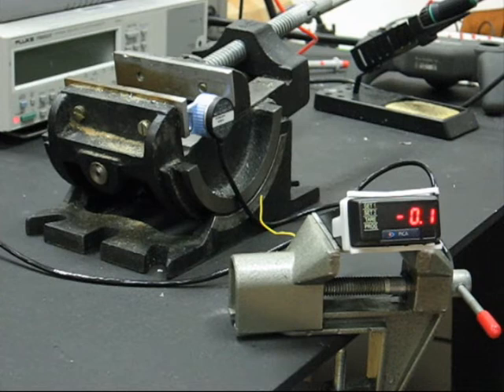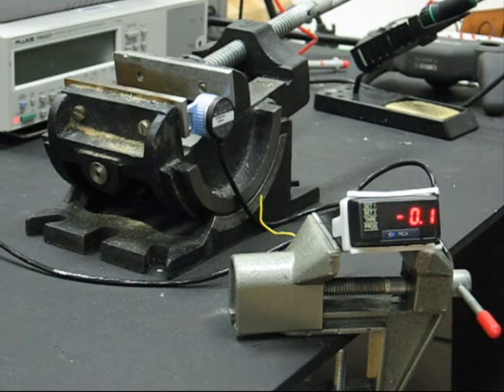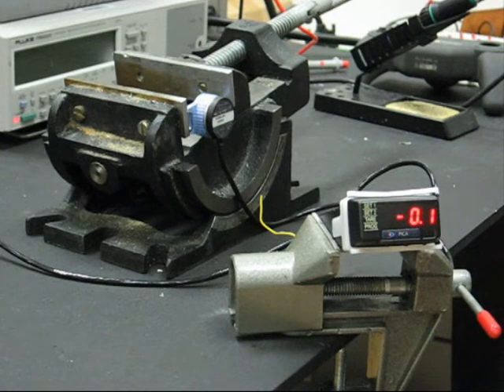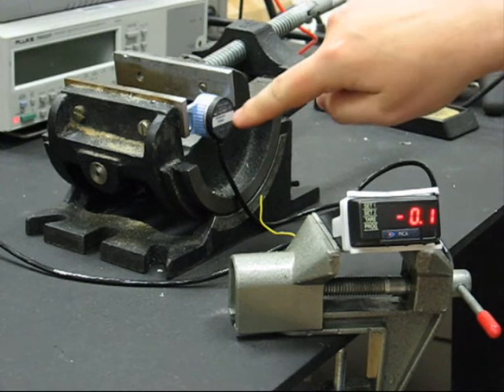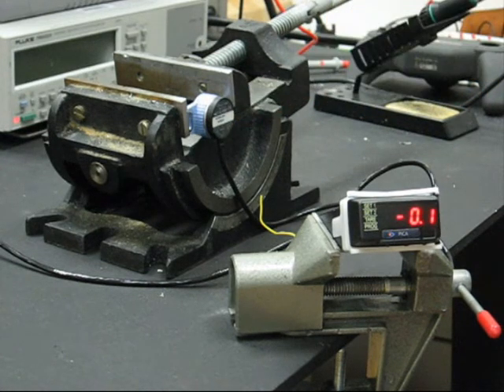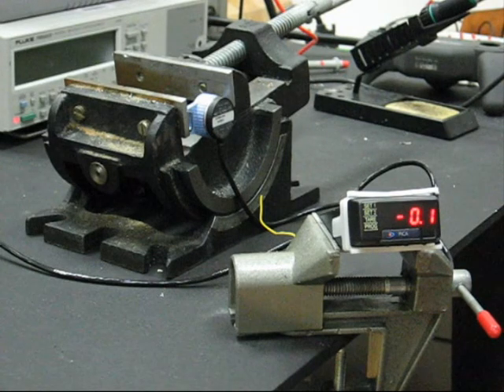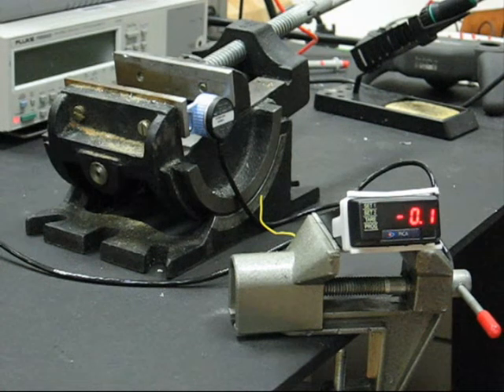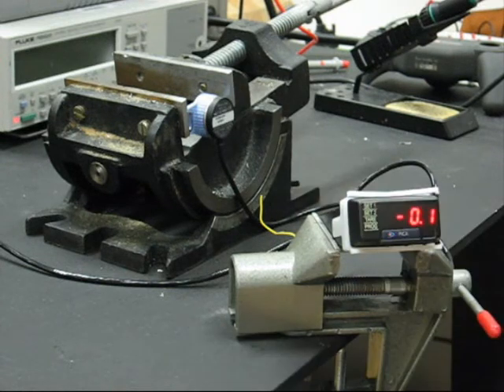But this device can actually handle anywhere from 8 to 30, conditions the voltage to the actual sensor and comes out as 0.5 to 4.5 volts across the voltage swing. So this is a 10 degree sensor, it's plus minus 10 degrees. So in the middle you should expect 2.5 volts, at 10 degrees you should expect 4.5 and at half a volt you should expect minus 10 degrees.